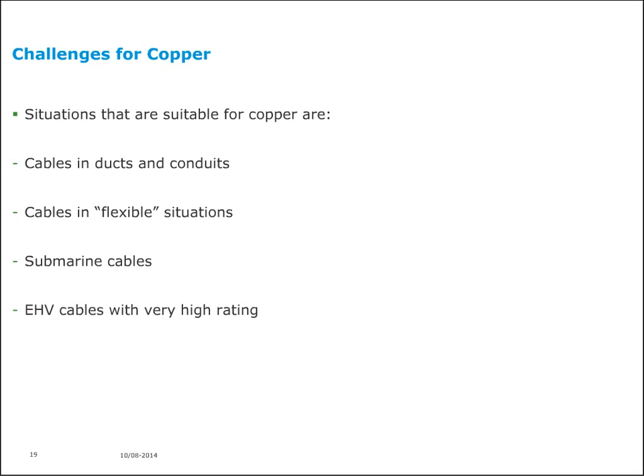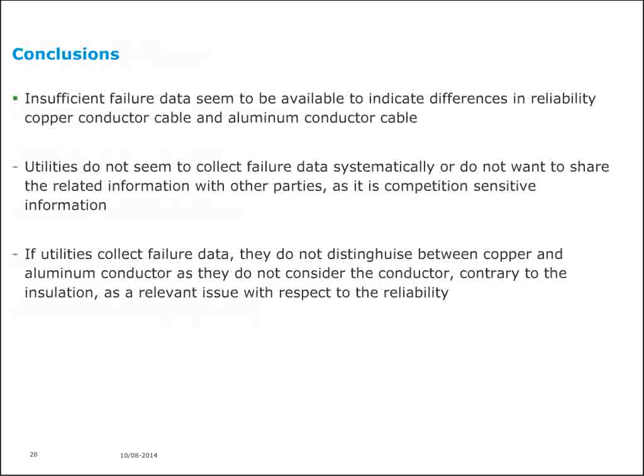There we see that almost entirely the copper conductor is selected because of the higher conductivity. And when you go for the extra high voltage cables, you have a thick cable because you have a lot of insulating material. Then you also make the conductor big, and the cable becomes very large in dimensions. So for extra high voltage cables, copper is a preferred conductor material. What are the conclusions of this brief presentation?